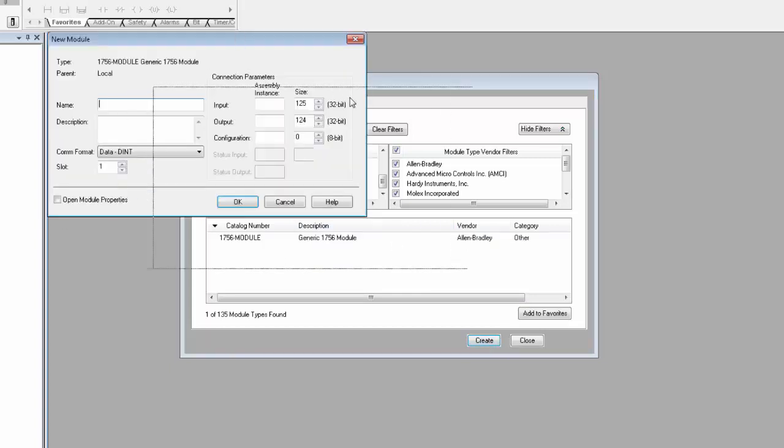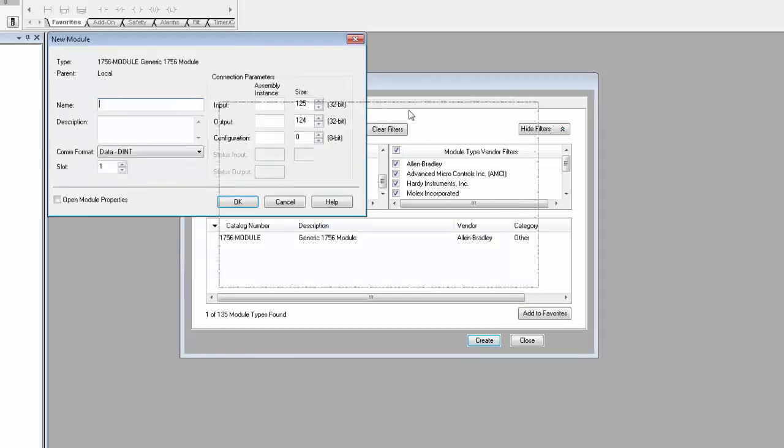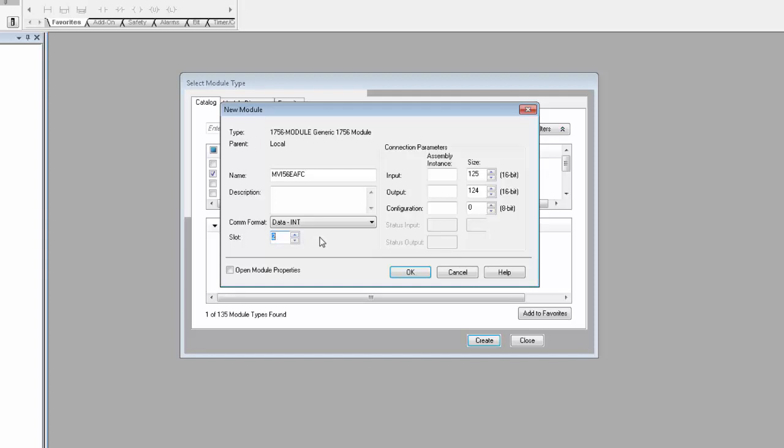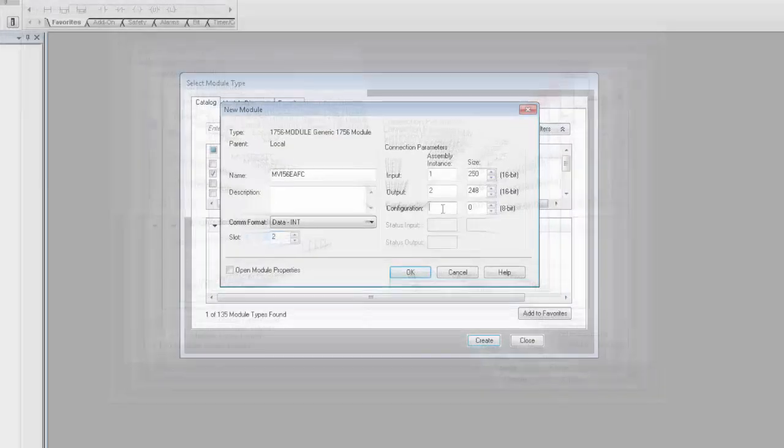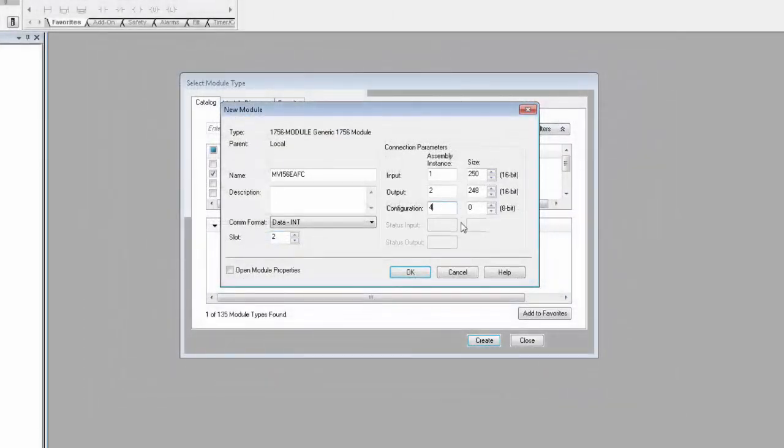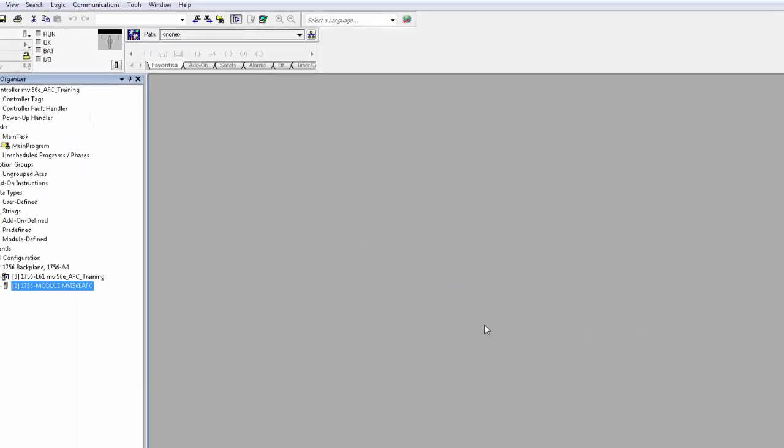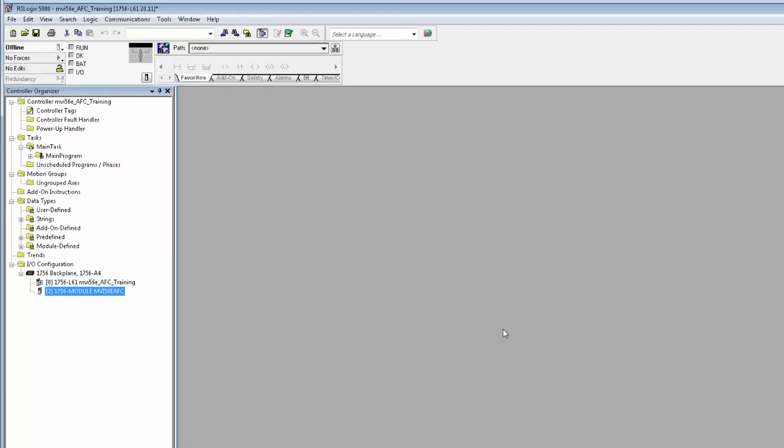On the New Module window, we'll give the module a name, MVI56E AFC. COM format should be set to Data Int. Select the slot where the AFC module resides in your rack. For me, it's in slot 2. Finally, the connection parameters should match what I have here. If you need to make an adjustment to the RPI setting for your application, you should do that as well. It is not recommended you use an RPI setting below 5MS. When you're finished, click OK and close. Now we have the MVI56E AFC module under the IO Configuration folder.